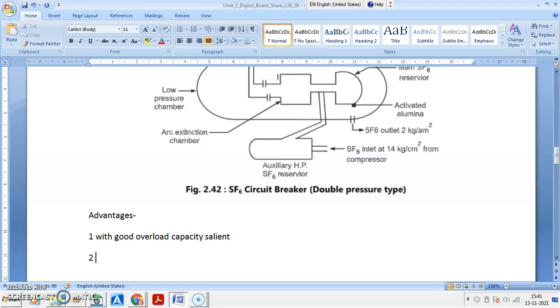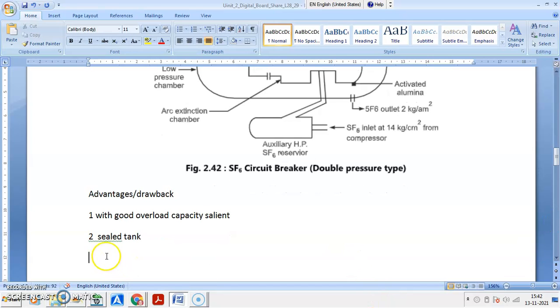Okay. Then there is failure of insulating strength because of moisture content. So I will combinedly write advantages and disadvantages, the drawbacks. Moisture can enter inside the tank if it is not sealed well. So a sealed tank is very important. If it is not, moisture can enter inside the contacts, inside the arcing chamber.